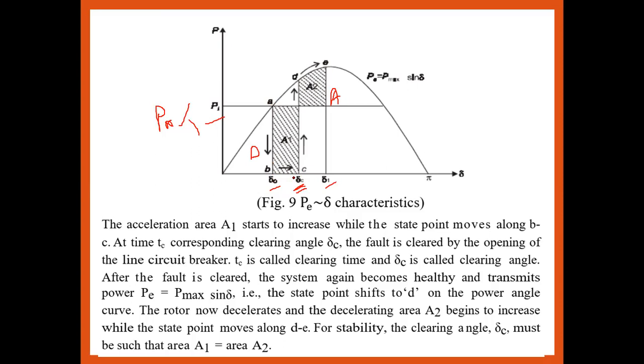The condition where the fault is cleared starts at point B and at the point of tc the corresponding clearing time is tc. So the time taken by the circuit breaker to clear the fault is called clearing time tc, and the corresponding angle is called clearing angle delta-c. After the fault is cleared, delta continues to rise, and Pe rises again — P equals Pmax times sin(delta) — from C to D then D to E. At point D on the power-angle curve, the rotor de-accelerates and the de-accelerating area A2 begins to increase.